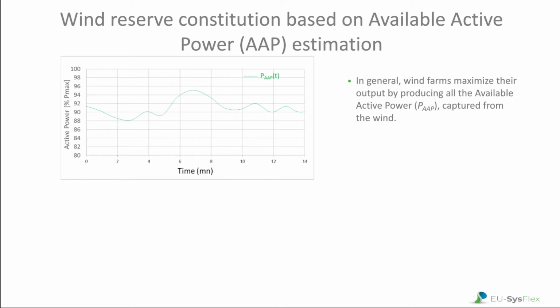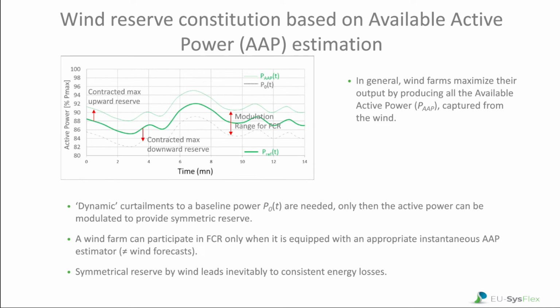These generators are designed to produce the maximum power that can be captured from the wind. So if they need to modulate their power according to the grid frequency, a dynamic curtailment of the generation should first be performed from the available active power, or the so-called AAP, which cannot be measured but only estimated in this case. Note that this AAP estimation is not a short-term wind power forecast and should be done on a per-second basis for wind reserve constitution.